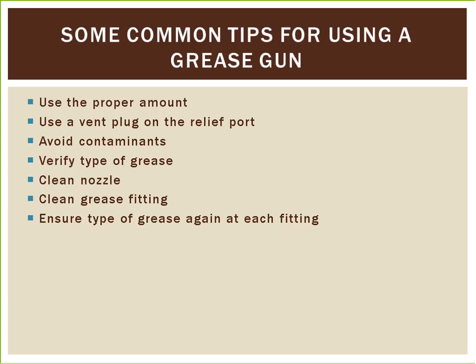Always make sure the dispensing nozzle of the grease gun is clean before using. Pump a small amount of grease out of the dispensing nozzle, then wipe off with a clean rag or lint-free cloth before attaching to the grease fitting. Next, clean the grease fitting of all dirt before attaching the grease gun. Inspect and replace damaged fittings. Also, clean the grease fitting after applying grease. It is helpful to use grease fitting caps to keep them clean, but still wipe fittings clean before applying grease.